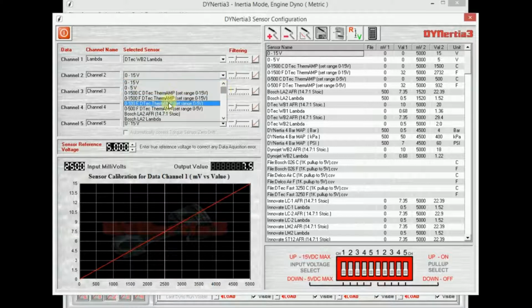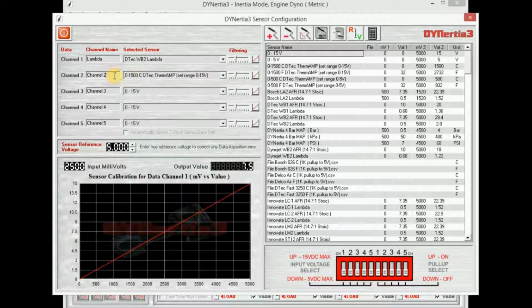This one here we might leave on voltage. I'm using the 0 to 15 volt range, so I'd need to go and switch channel 3's switch to the upright position on my hardware. Anytime I wish to see the calibration for these channels, I can click on the graph symbol next to it and it will show the calibration down the bottom.